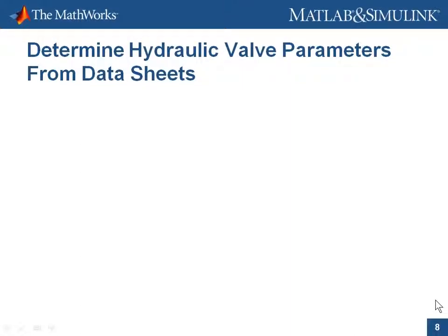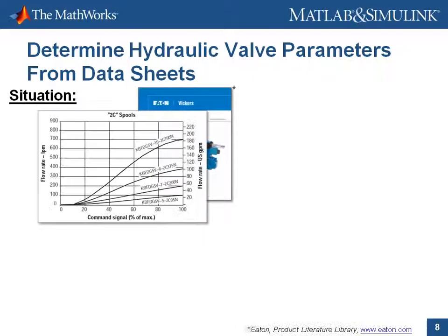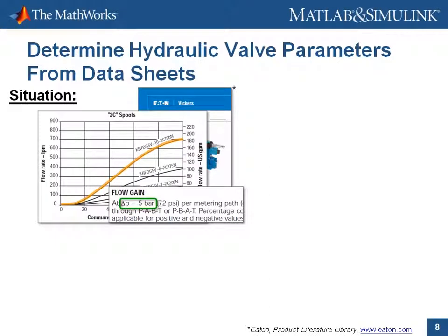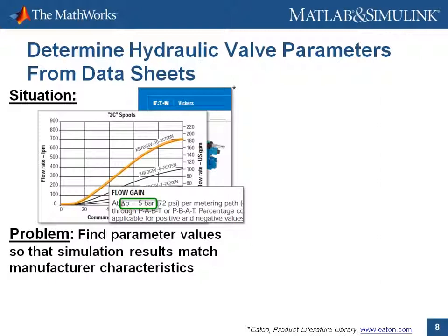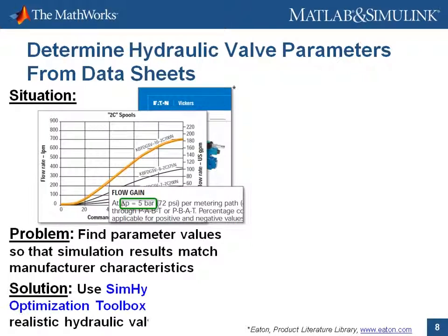In this demonstration, we're going to show how you can use optimization algorithms to determine hydraulic valve parameters from data sheets. We have a hydraulic data sheet that shows a series of flow characteristics. These curves represent the relationship between the control signal applied to the hydraulic valve and the flow rate through the valve. From the data sheet, we can also see that a pressure differential of 5 bar was maintained across the metering path. Using this information, we need to set up a model so that we can determine parameter values that will enable the simulation results to match this manufacturer characteristic. We're going to use SimHydraulics and the Optimization Toolbox to do that.